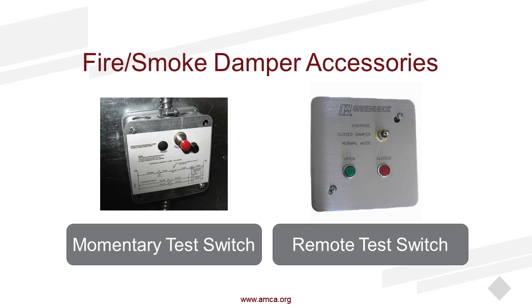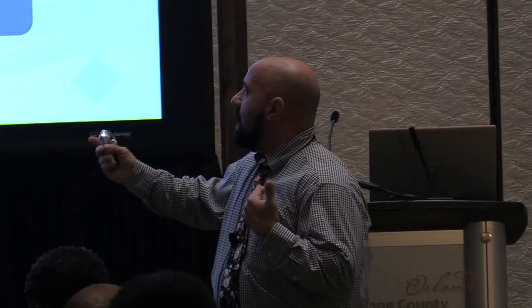So for hospitals, educational, institutional, places with very large maintenance budgets, lots of dampers, these options give the testing folks a lot of savings. So the momentary test switch is exactly that, momentary. It's a push button. I climb up on a ladder, I push a button. As my finger is holding that button down, I'm breaking that circuit. I'm losing power to my actuator.